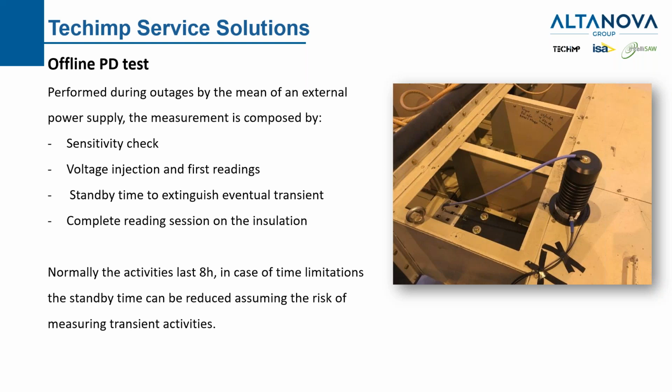If I can put my personal opinion, in this case, sometimes an offline test costs more than a sensor installation and an online test. And it's just a once-in-a-lifetime offline test. If I come to your plant, I test with my equipment, my sensor, my acquisition unit, I will get some readings, but it will be harder to compare with the next service company. I always prefer at least to have a permanently installed sensor.